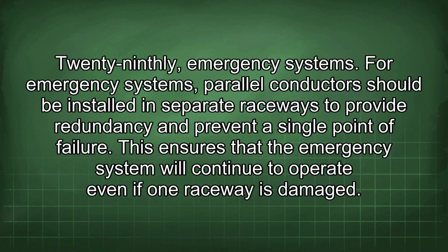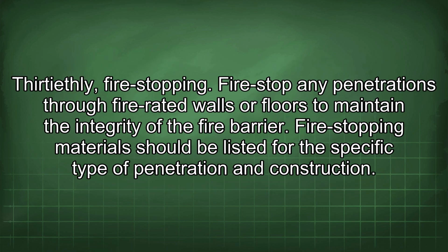29th, emergency systems. For emergency systems, parallel conductors should be installed in separate raceways to provide redundancy and prevent a single point of failure. This ensures that the emergency system will continue to operate even if one raceway is damaged. 30th, fire stopping. Fire stop any penetrations through fire-rated walls or floors to maintain the integrity of the fire barrier. Fire stopping material should be listed for the specific type of penetration and construction.